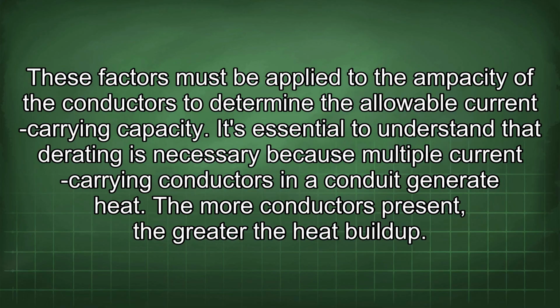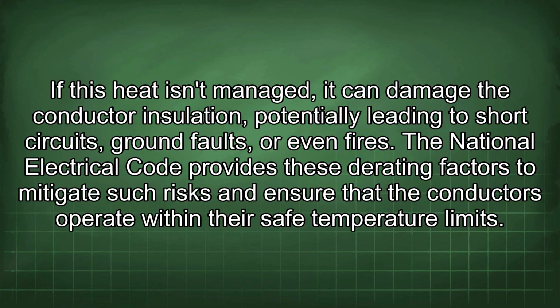It's essential to understand that derating is necessary because multiple current carrying conductors in a conduit generate heat. The more conductors present, the greater the heat buildup. If this heat isn't managed, it can damage the conductor insulation, potentially leading to short circuits, ground faults, or even fires.